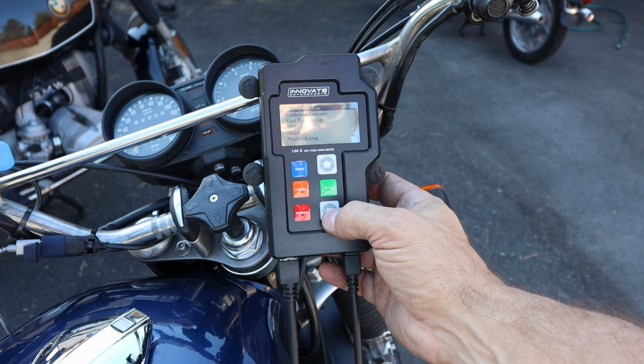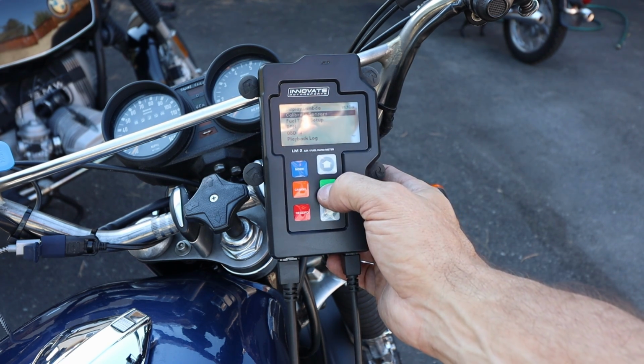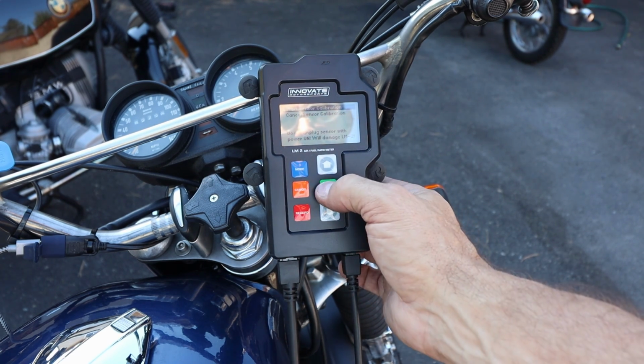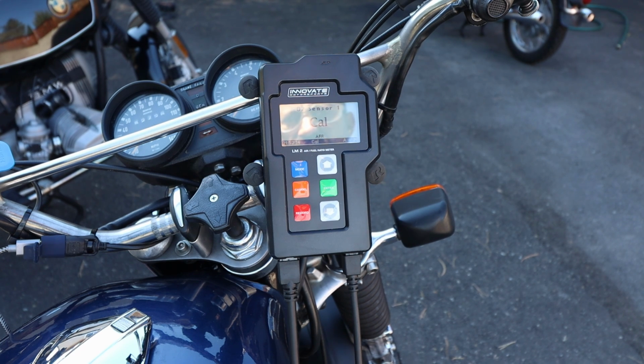Multiple sensors can be hooked up. Here, calibrate sensor - we go to calibrate, press enter, start calibration. And now it's calibrating the sensor. Once you get a 20.9, you're right where you need to be.